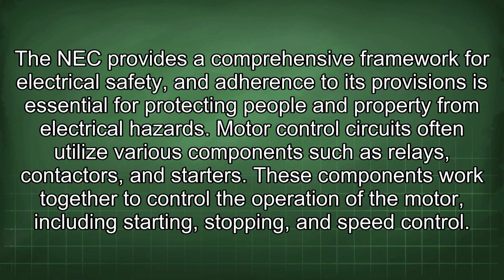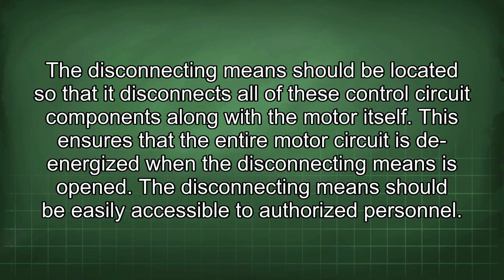The NEC provides a comprehensive framework for electrical safety, and adherence to its provisions is essential for protecting people and property from electrical hazards. Motor control circuits often utilize various components such as relays, contactors, and starters. These components work together to control the operation of the motor, including starting, stopping, and speed control. The disconnecting means should be located so that it disconnects all of these control circuit components along with the motor itself. This ensures that the entire motor circuit is de-energized when the disconnecting means is opened.